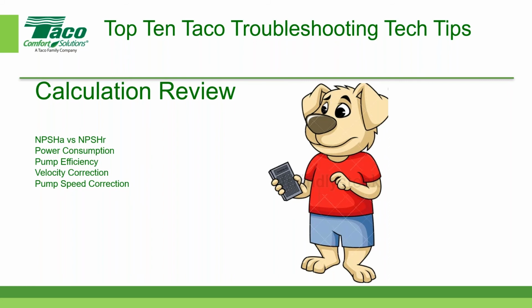And you'd also have to make a pump speed correction, because the pump is tested at 1760 RPM, but not all electric motors will spin at full load at 1760. Some might spin at a higher speed, especially some of these premium efficiency motors. They might actually spin at 1780. I've seen some at 1785 RPM. So the more efficient the motor is, the higher the rotational speed. So if there's a higher speed, it has to be corrected for the speed.